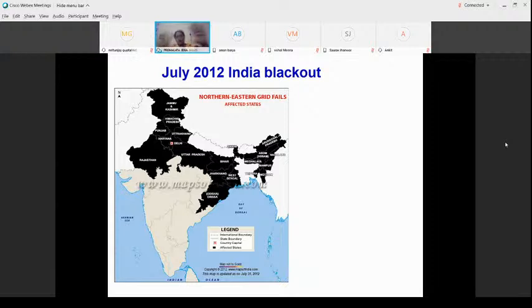So the whole northern grid and northeast grid together were under a blackout situation. Blackout means there is no supply, no generation, nothing. And you remember what kind of situation it is. If in your room or office or at your home the supply is not there for 1 minute, how do you feel? You can't tolerate it even for a minute. So for 2 days they were under a blackout situation, a lot of money was lost, and a lot of people were in trouble. We call them critical loads, priority loads and non-priority loads. The critical loads are those loads which demand the supply as quickly as possible.